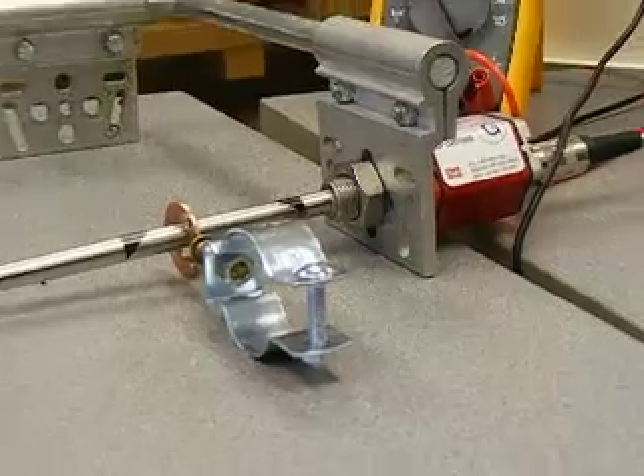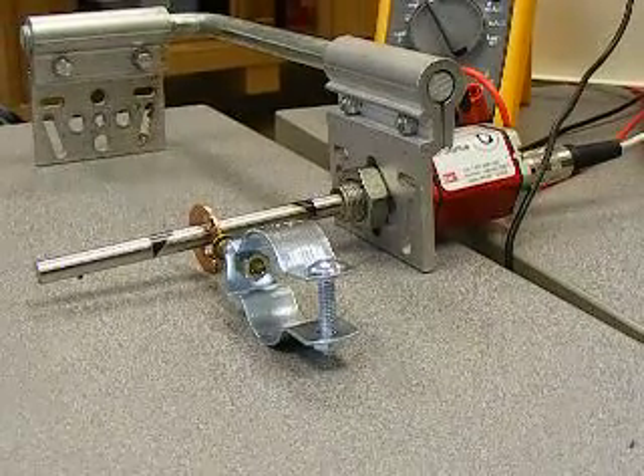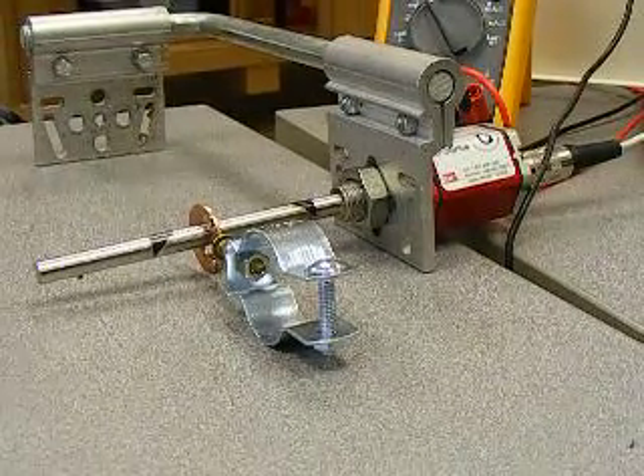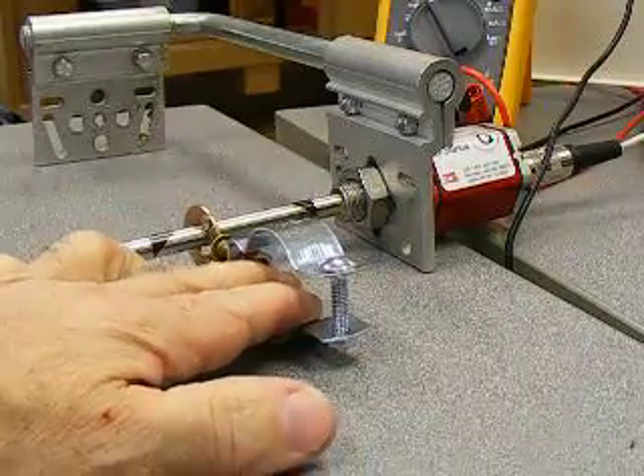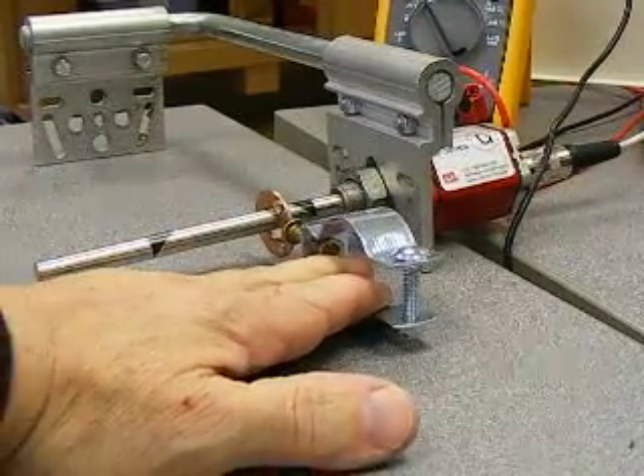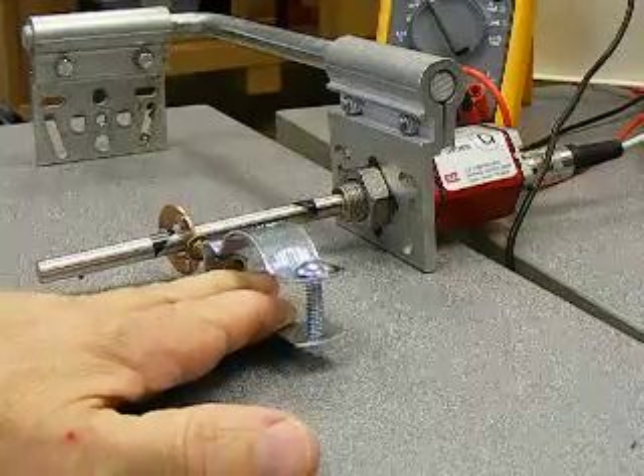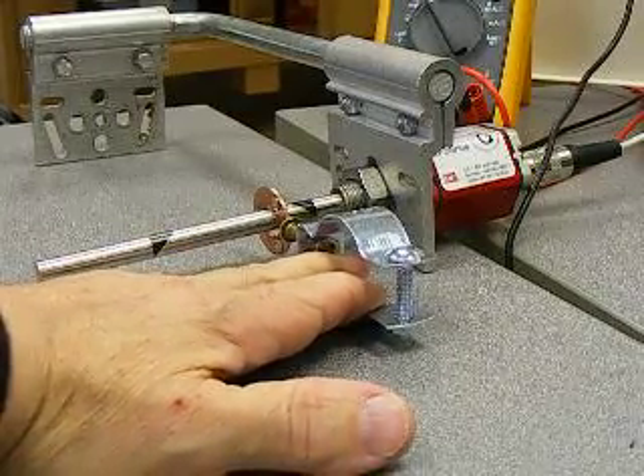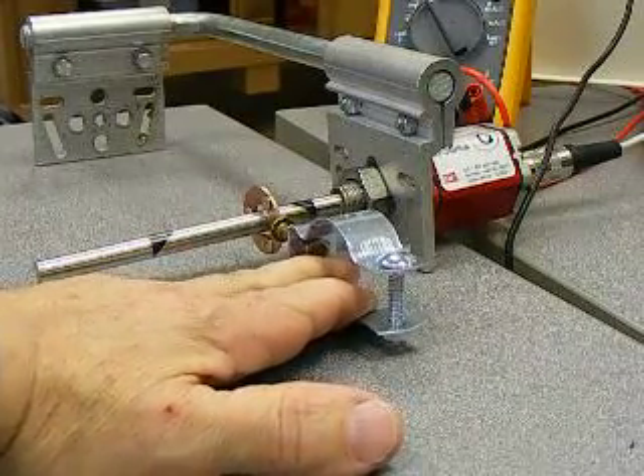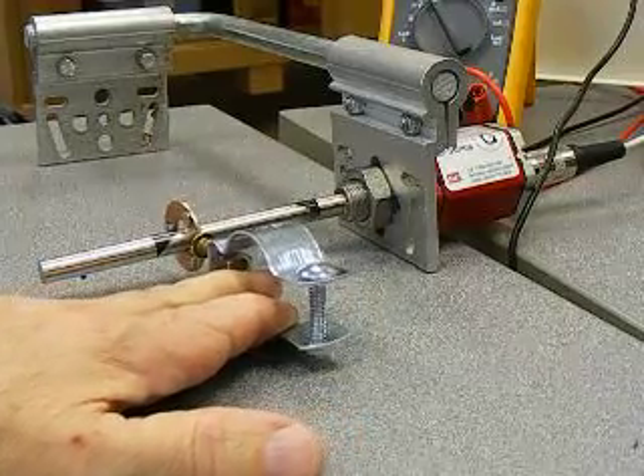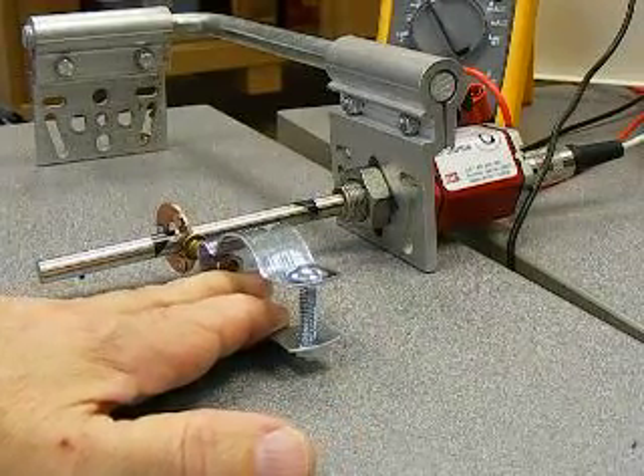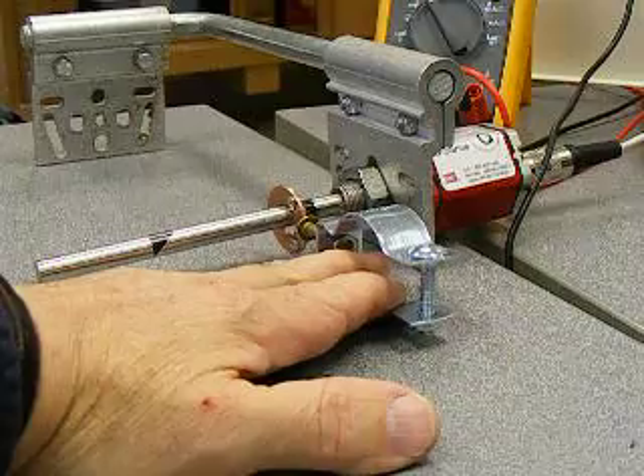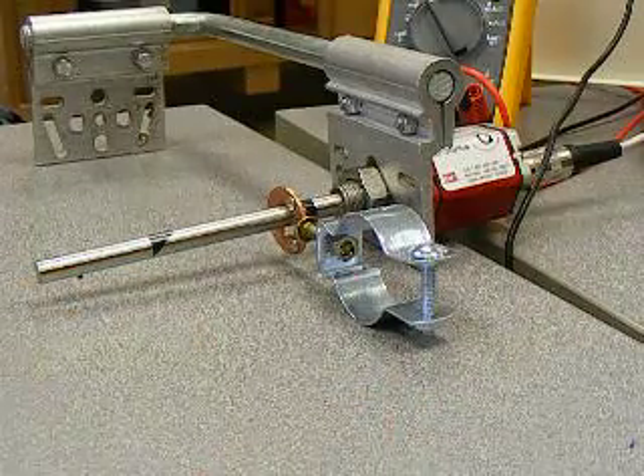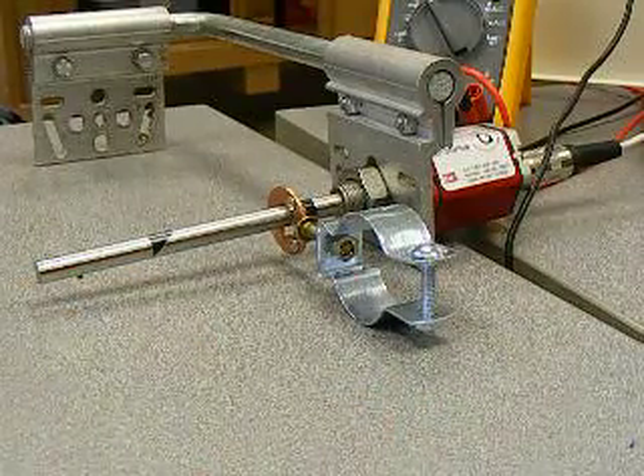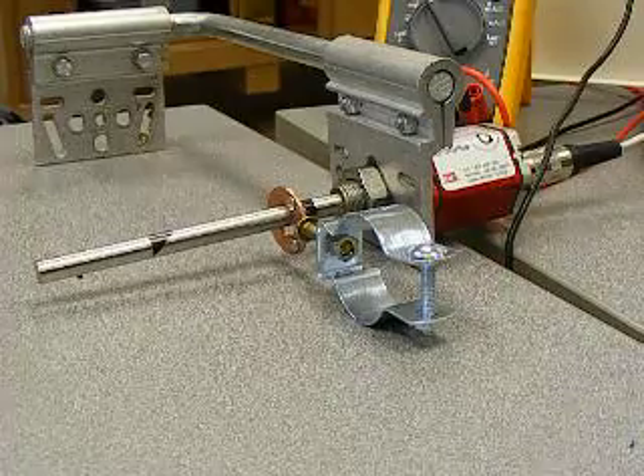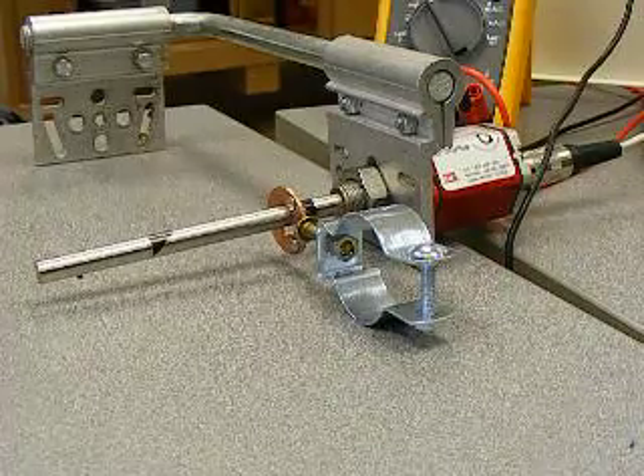Let me back out a little bit so that you can see it. This is a Temposonics G series. This will attach to the spear valve. The magnets are embedded in that copper washer that you see sliding over the shaft. So at this end I get 10 volts. At this end I get 0 volts. That gets divided out and sent as a 0 to 5 volt signal to the input on the module.